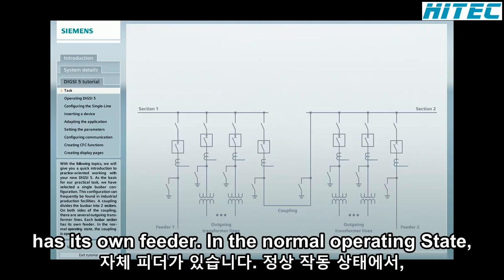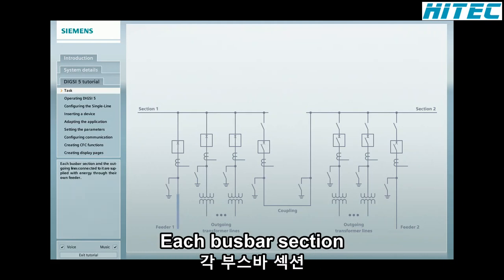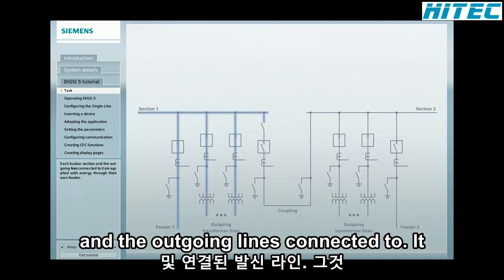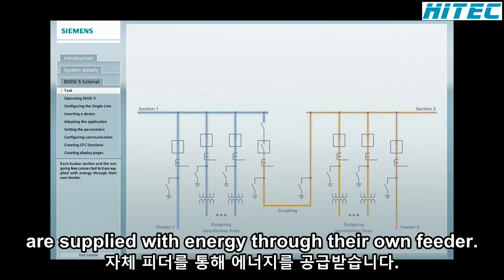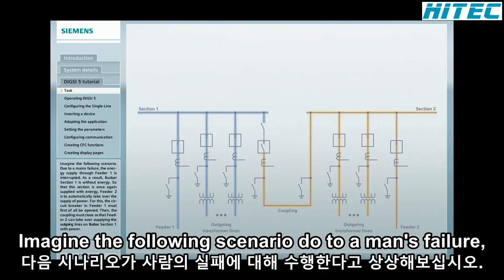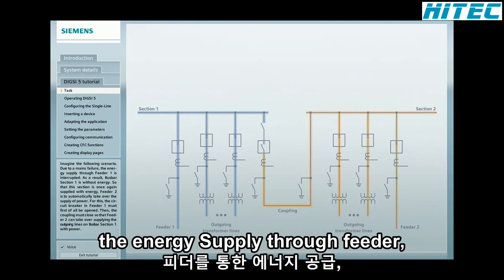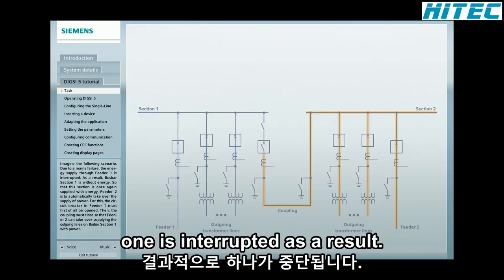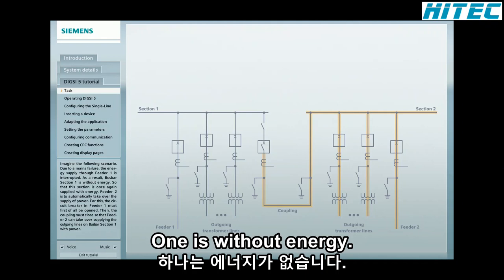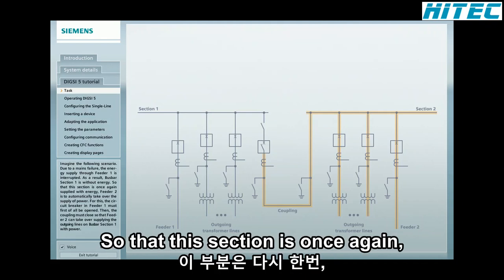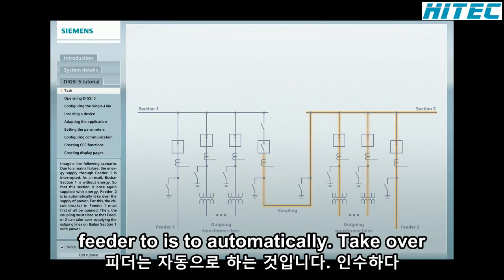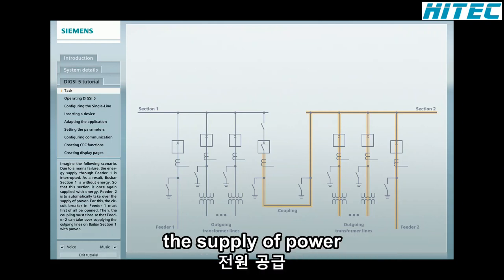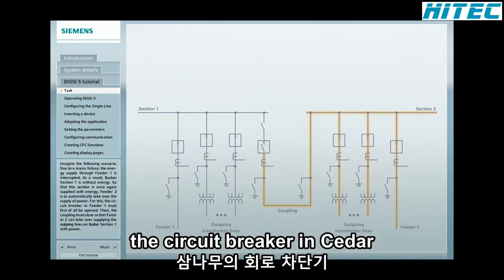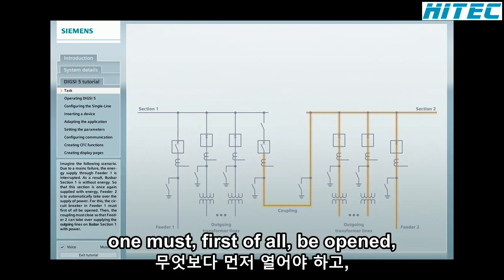In the normal operating state, the coupling is open. Each busbar section and the outgoing lines connected to it are supplied with energy through their own feeder. Imagine the following scenario. Due to a mains failure, the energy supply through feeder 1 is interrupted. As a result, busbar section 1 is without energy. So that this section is once again supplied with energy, feeder 2 is to automatically take over the supply of power. For this, the circuit breaker in feeder 1 must first of all be opened.